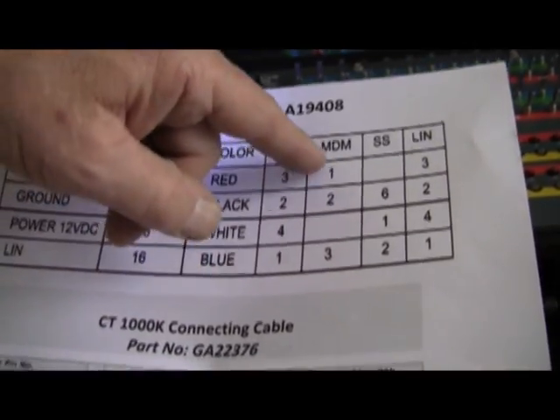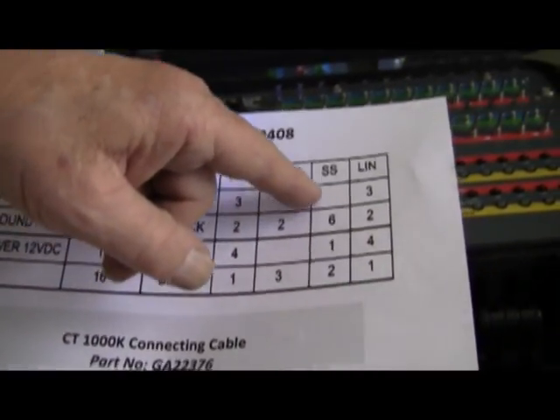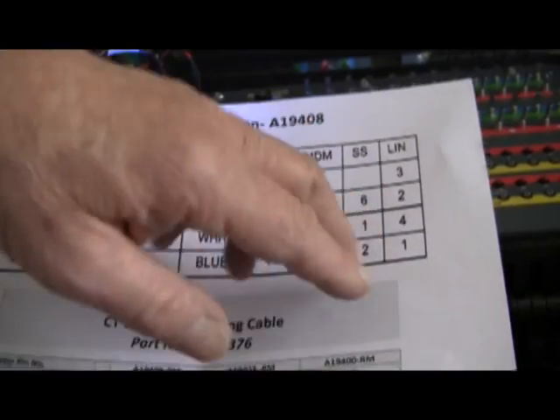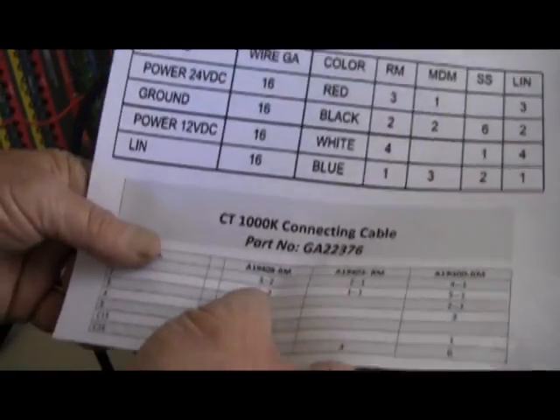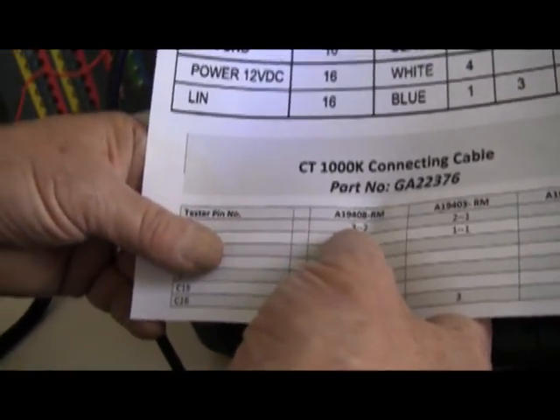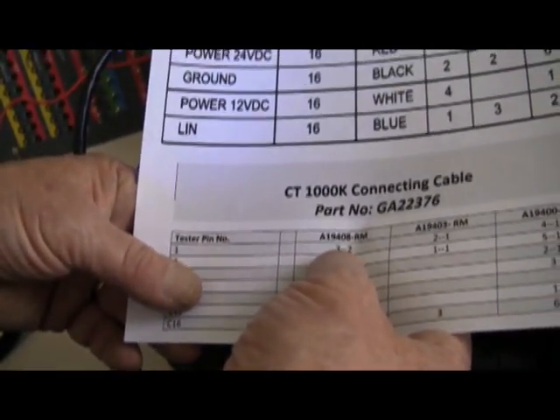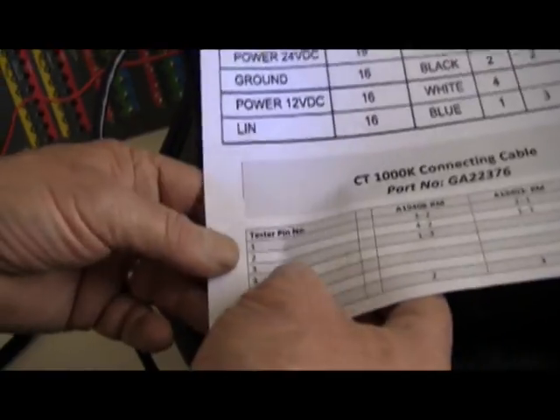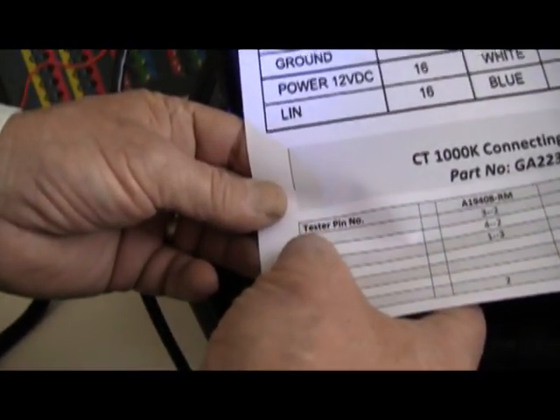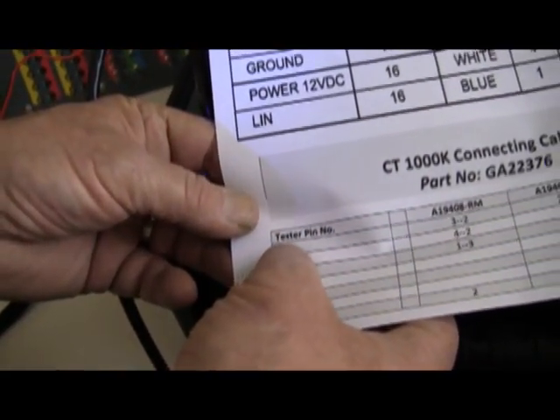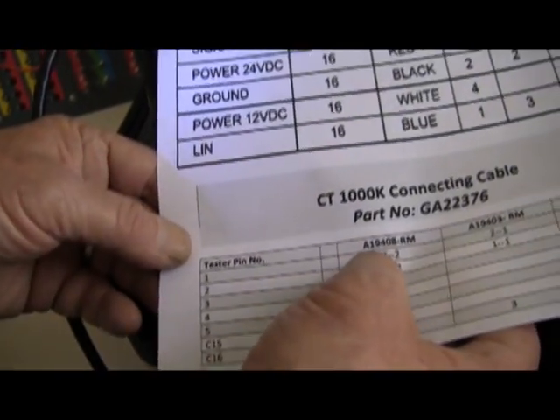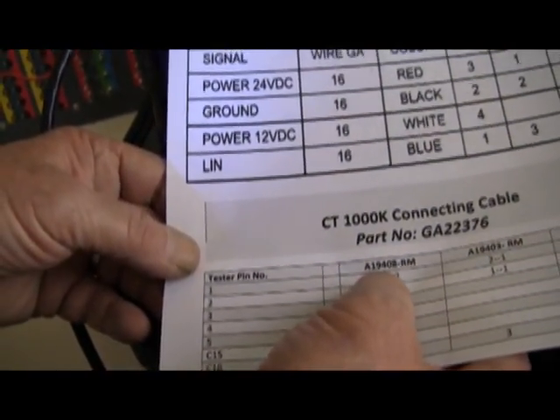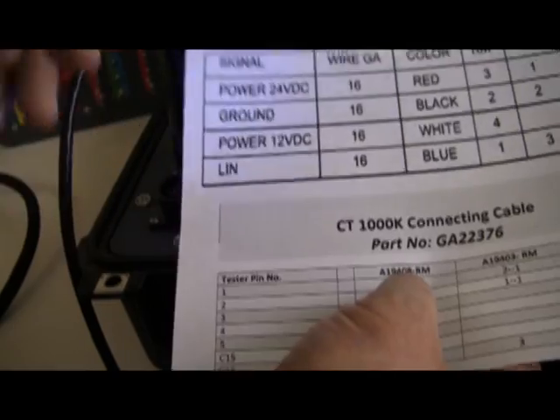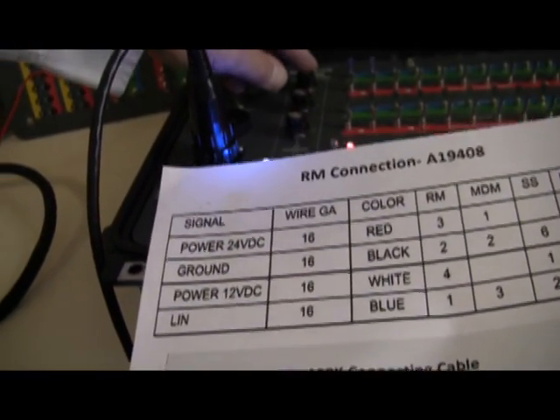When we check out to the MDM, or really any of these, there's multiple pieces hooked to each wire. So on the chart, when you set up the tester for any of these cable harnesses, what we're looking at is pin number 1 on the tester harness becomes wire number 3, which has 2 terminators. That's what these switches are used for here.